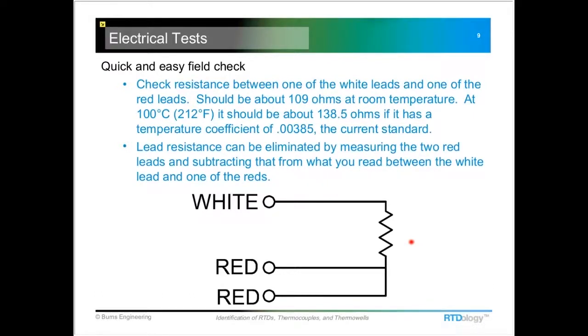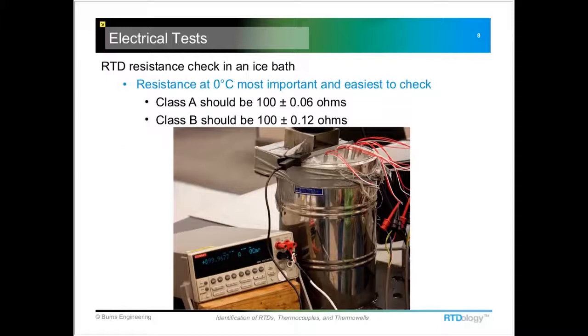And now that resistance, if it's what's called a Class A sensor, should be 100 ohms plus or minus .06. If it's a Class B, it'll be 100 plus or minus .12, and that's at the ice point.